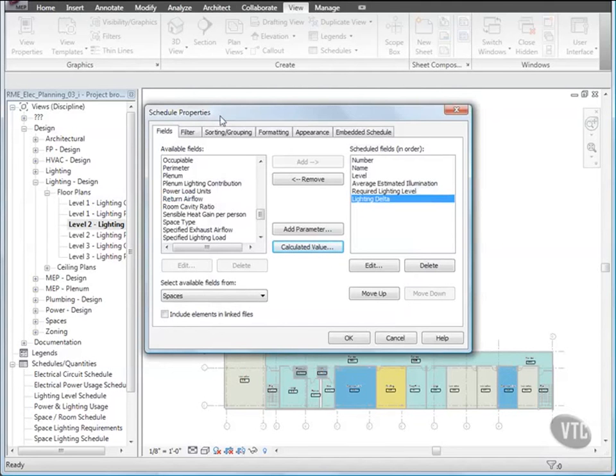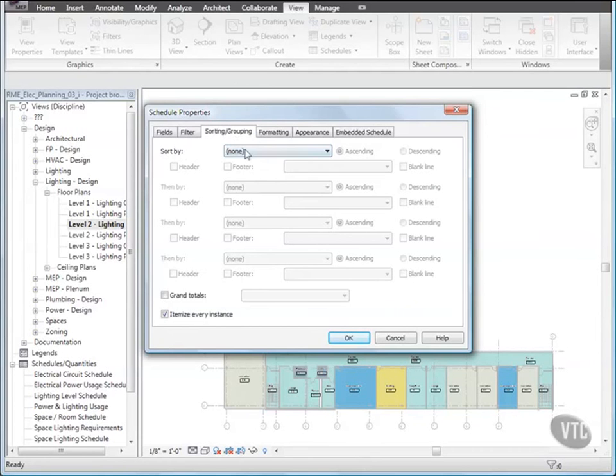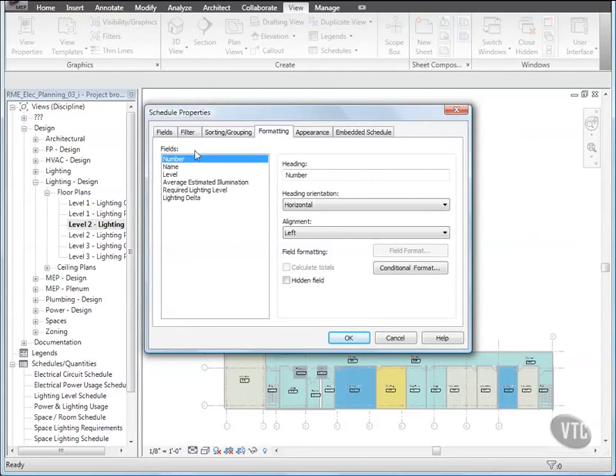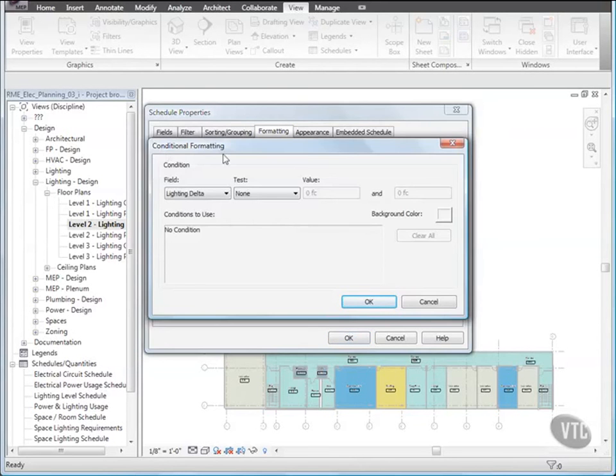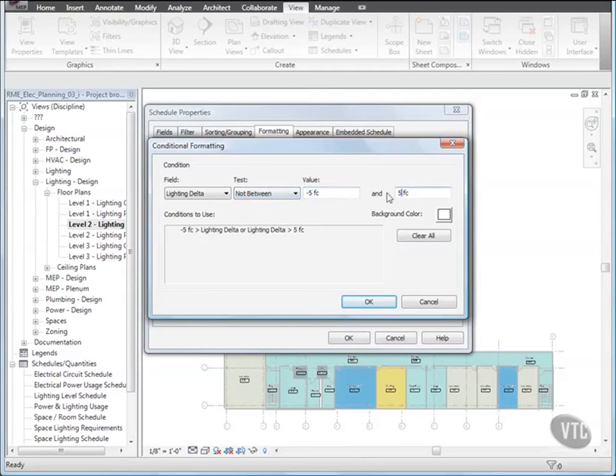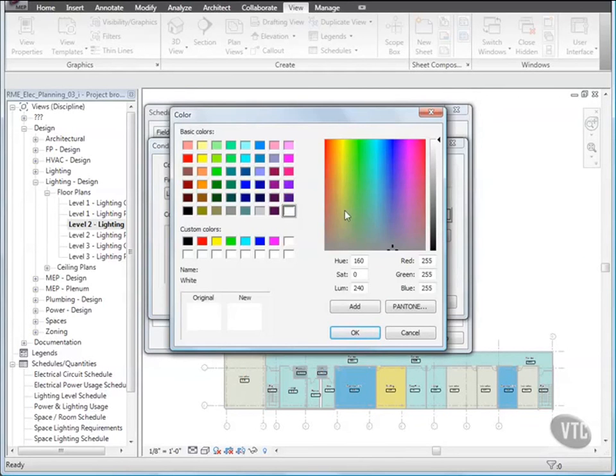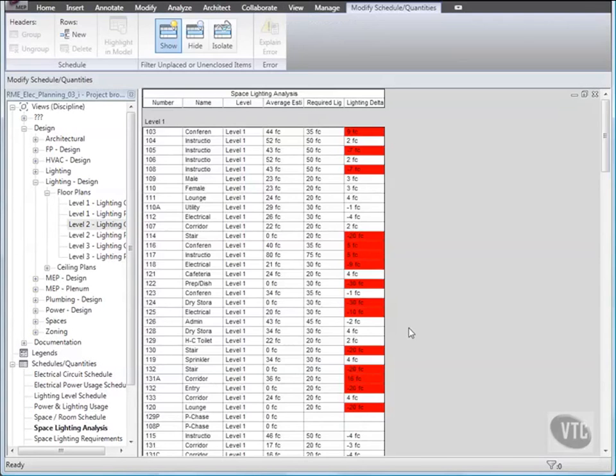Back in the Schedule Properties dialog, click the Sorting or Grouping tab, and for Sort By, select Level, and then select Header, and Blank Line. Then, click the Formatting tab, and for Fields, select Lighting Delta, and click Conditional Format. In the Conditional Format dialog, under Condition, for Test, select Not Between. And for Value, enter Negative 5, and 5, and then click Background Color, and under Custom Colors, select Red, and click OK three times. The Lighting Delta values that are not within the Conditional Value of Negative 5 and 5 are highlighted in red.